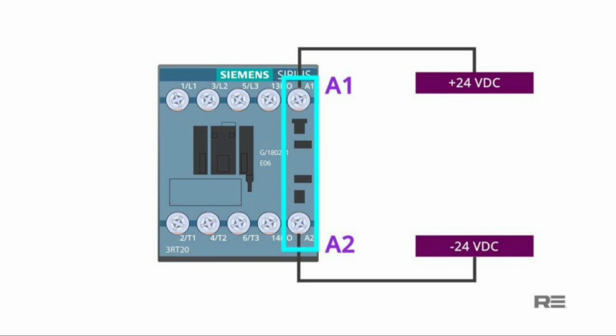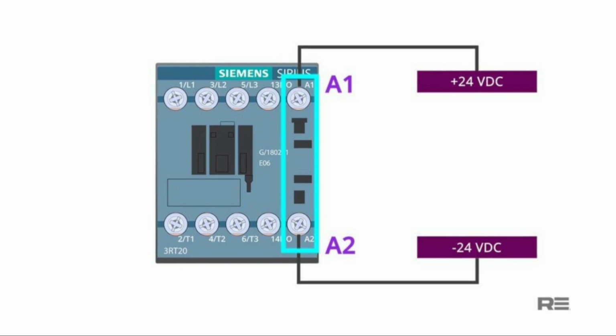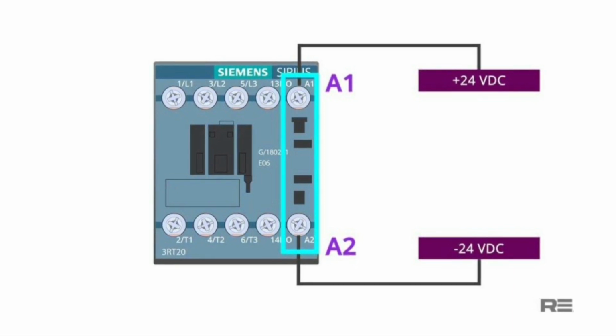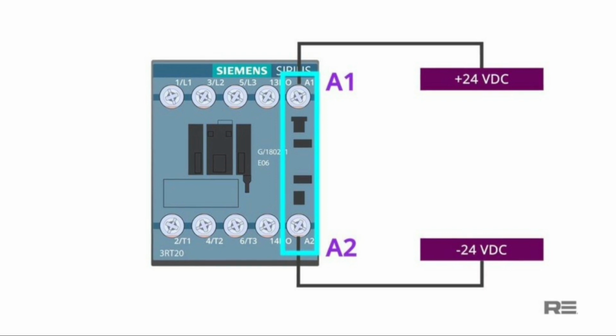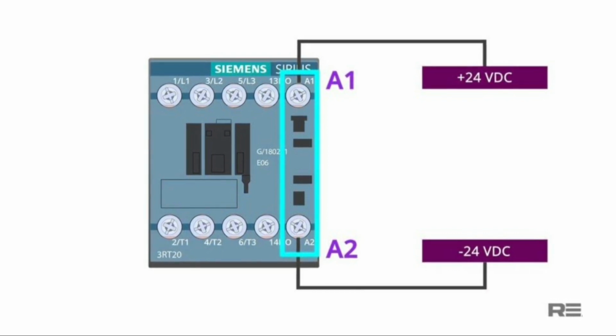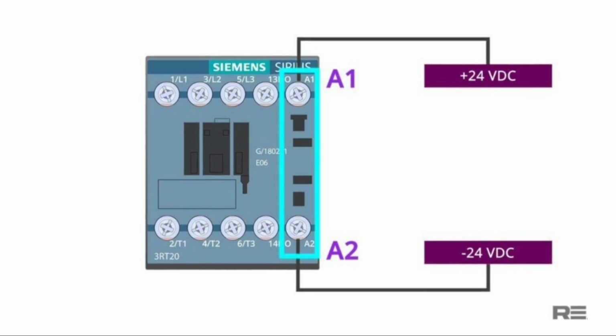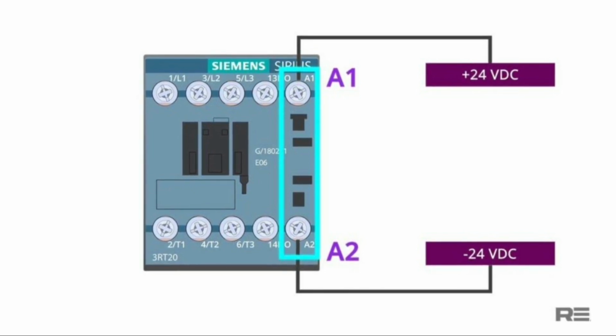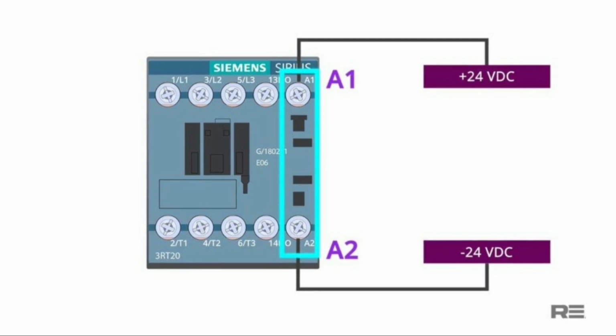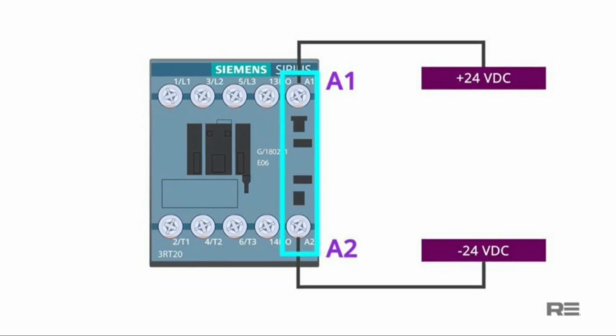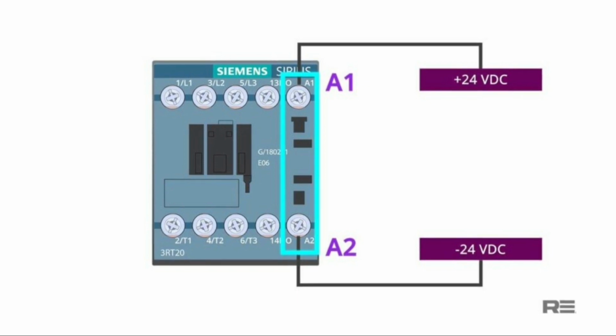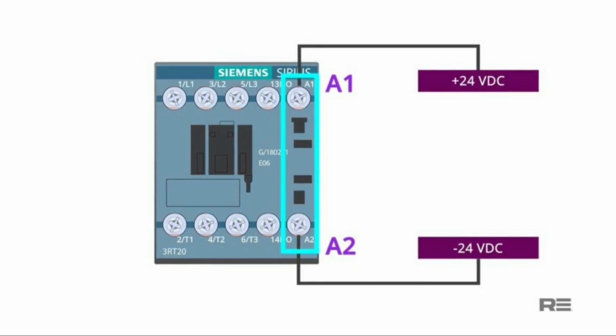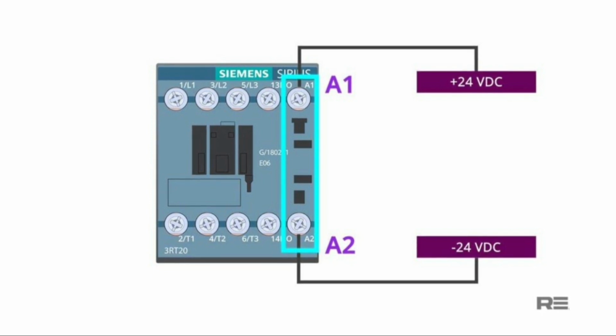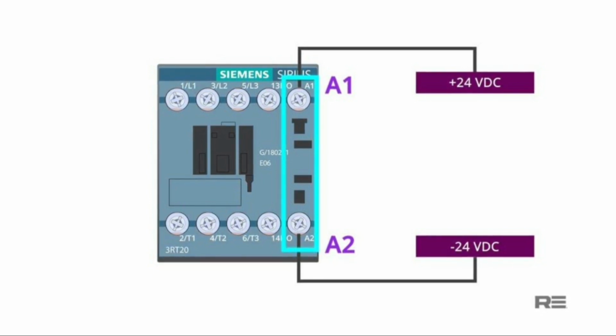Obviously, the reason that we are connecting a 24-volt DC power to these terminals is that the coil works with a 24-volt DC power for this contactor. For some other contactors, this coil may work with different voltages such as 12-volt DC or maybe 220-volt DC. Depending on the type of the contactor, the coil can also work with AC voltage. For example, the contactor's coil may work with a 24, 120, or 220-volt AC power. So before connecting the wires to the coil, you first need to check the coil voltage. Most of the contactors, like the one we have here, work with a 24-volt DC power.